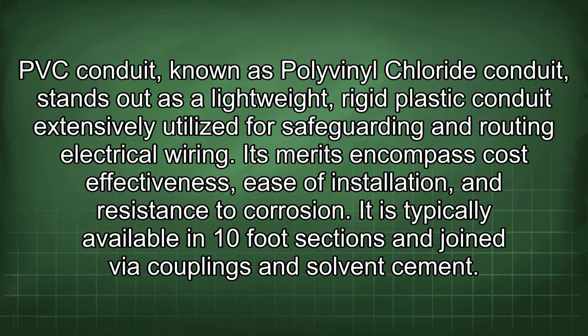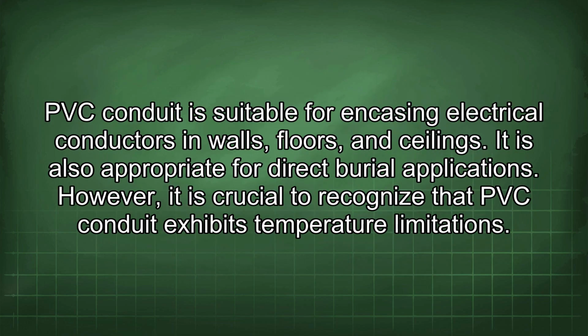PVC conduit, known as polyvinyl chloride conduit, stands out as a lightweight, rigid plastic conduit extensively utilized for safeguarding and routing electrical wiring. Its merits encompass cost-effectiveness, ease of installation, and resistance to corrosion. It is typically available in 10-foot sections and joined via couplings and solvent cement. PVC conduit is suitable for encasing electrical conductors in walls, floors, and ceilings. It is also appropriate for direct burial applications.